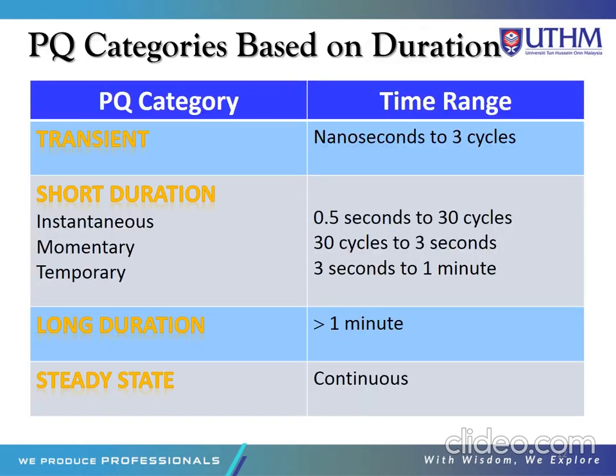Okay, these are the PQ categories based on duration. There are four categories here. The first one is transient, and the time range is nanoseconds to 3 cycles. The second one is short duration. There are three types of short duration. The first one is instantaneous, with a time range between 0.5 to 30 cycles. Then momentary, 30 cycles to 3 seconds. And temporary, with a time range of 3 seconds to 1 minute.